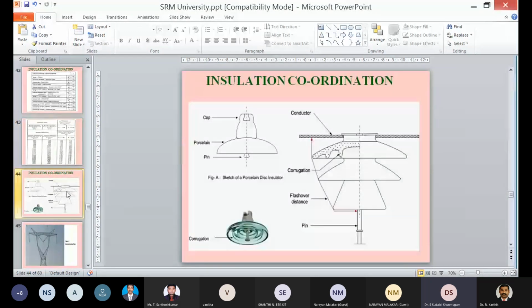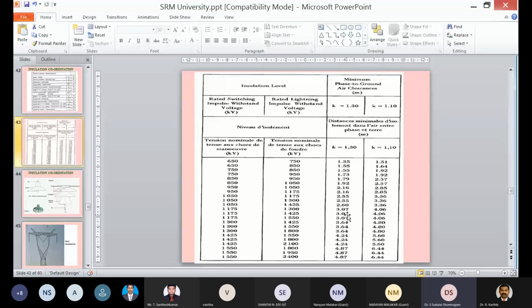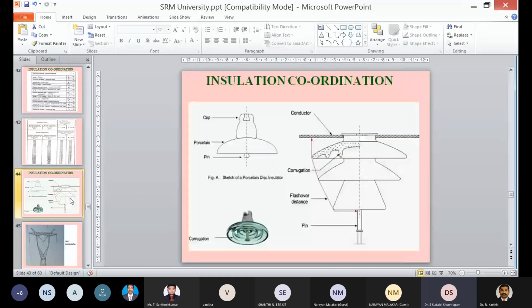Suppose you are taking a cap and pin insulator. The cap and pin insulator has a dry arcing distance, that is the cap to pin distance, of 145 mm. So roughly, for a 400 kV system, you can include 23 insulators; I am telling this on a rough calculation. For a standard drip design cap and pin insulator, the dry arcing distance is 145 mm. So within 3.07 meter, you can include only 23 to 24 insulators. That is why, in an actual 400 kV system, if you count the number of insulators between line and ground, the number will be around 23 to 24.